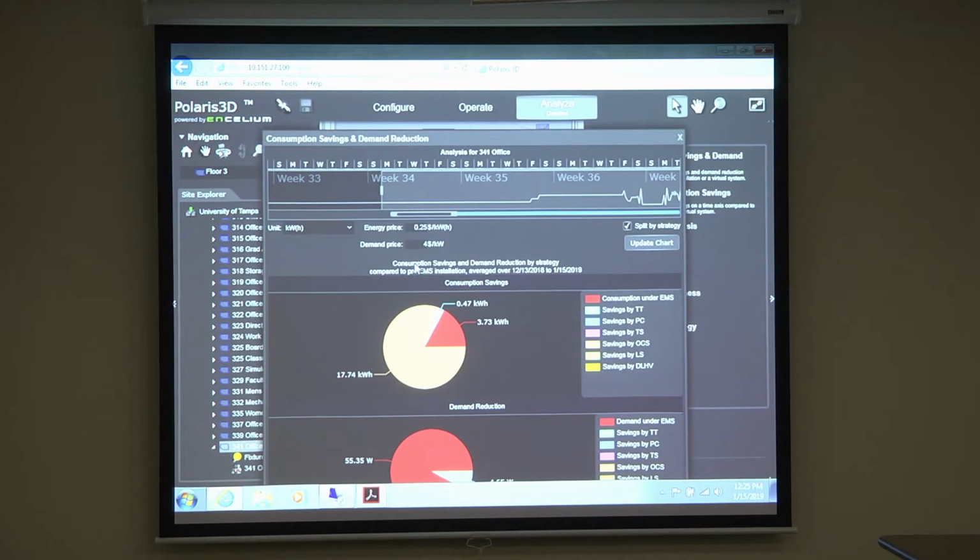In theory, you're saving 20% by bringing it down to 80%. There's some math and other stuff that's not direct. It's probably a little bit logarithmic, right? So it's not direct, but just keep the math simple. That's kind of what it's going to be doing. So we cap off at 80%, 20% savings is task tuning right off the back. That's pretty much what it is.